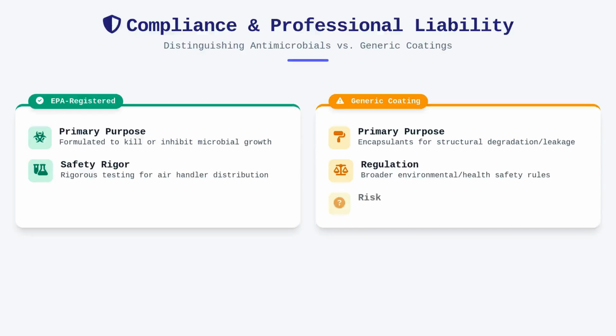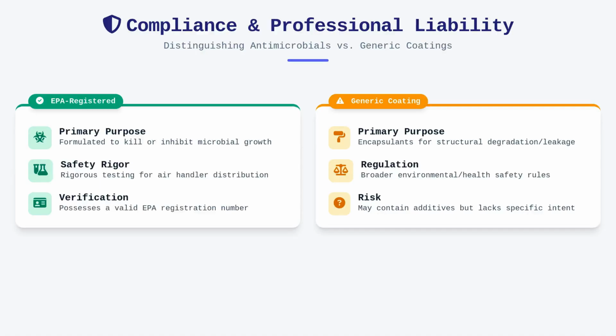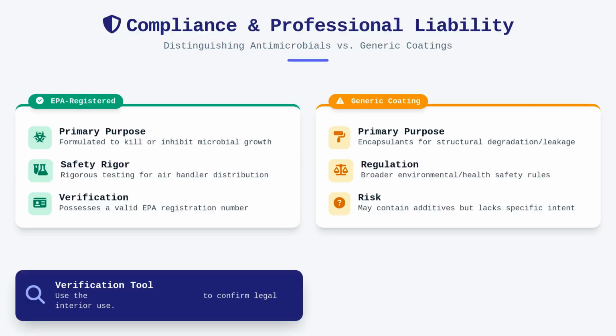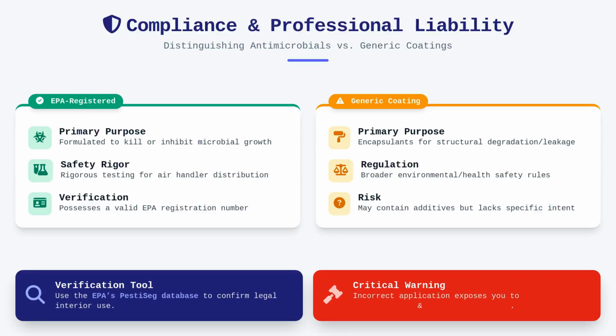You must verify that any substance you apply is not just a general-purpose cleaner, but possesses a valid EPA registration number that confirms it has been evaluated for human occupancy safety. If you are ever in doubt about the status of a chemical, the EPA's Pesticide database provides clear verification of whether a product is legally permitted for interior air system applications. Using a product that is not registered for your specific intent exposes you and your client to significant potential for legal repercussions and health liabilities.